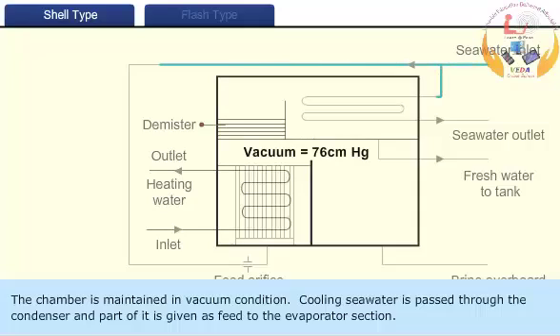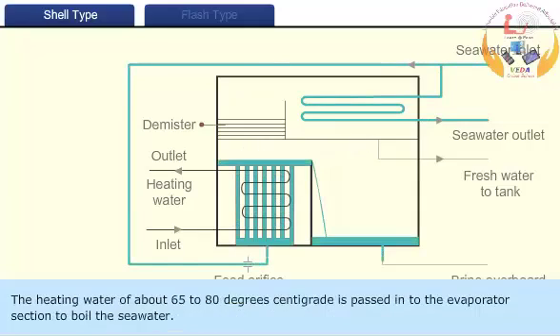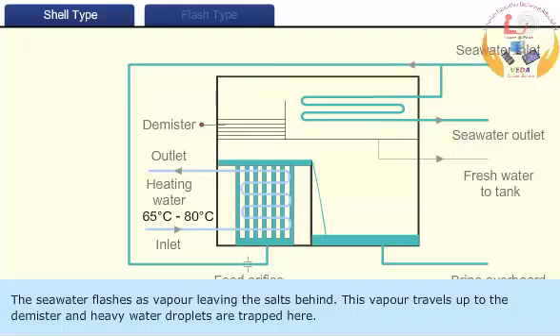Cooling seawater is passed through the condenser and part of it is given as feed to the evaporator section. The heating water of about 65 to 80 degrees centigrade is passed into the evaporator section to boil the seawater. The seawater flashes as vapor, leaving the salts behind.